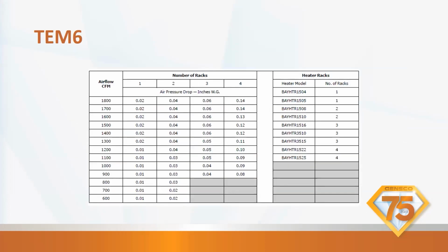So if you look on here, the number of racks, if you have 3 racks, it's going to drop your pressure on an 1800 CFM at 0.06. So you have to subtract that from your total airflow. The number that you have on your chart, if you measured 0.7 and you're trying to determine your correct airflow, you need to take the 0.06 off that 0.7. So it's actually going to be 0.64 instead of 0.7, right?